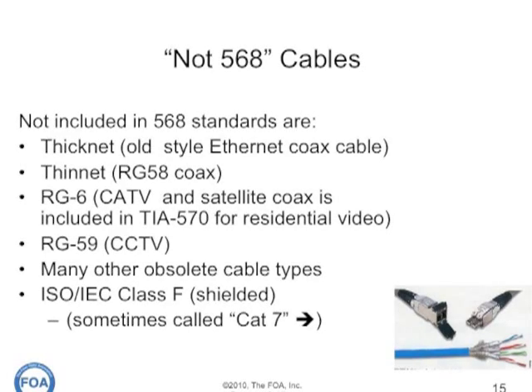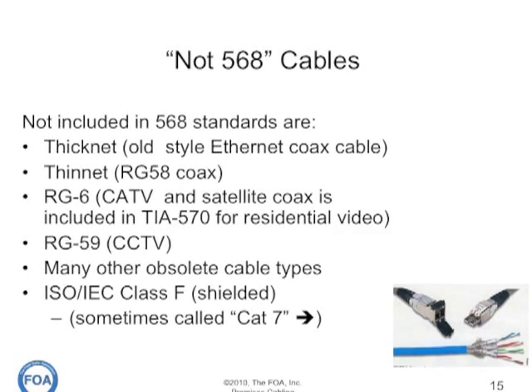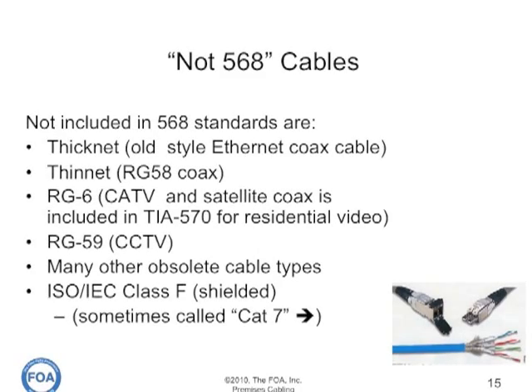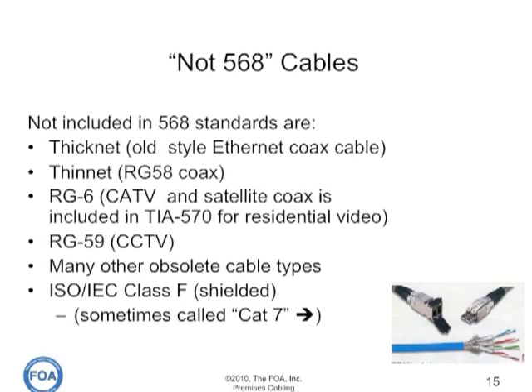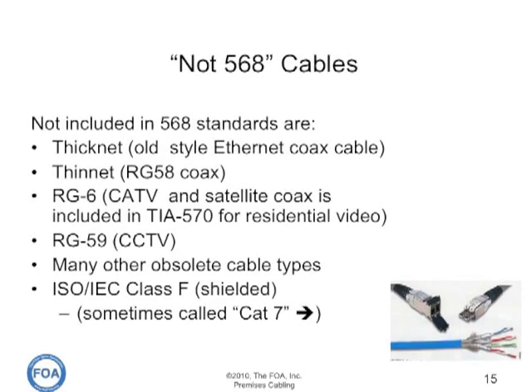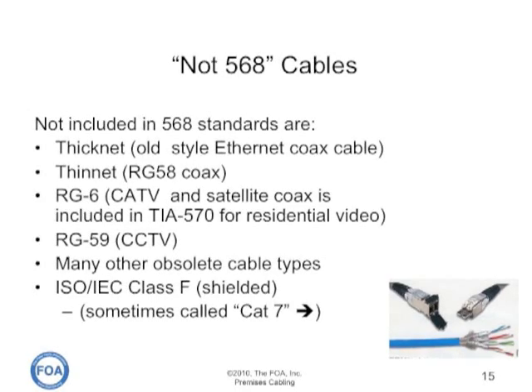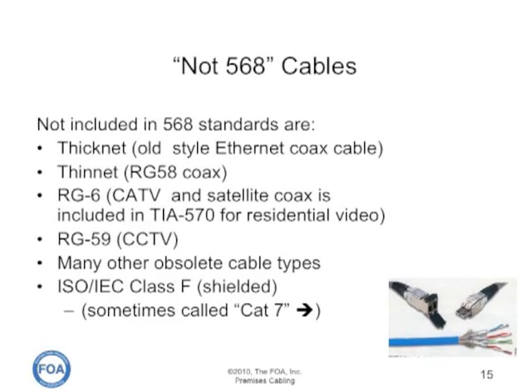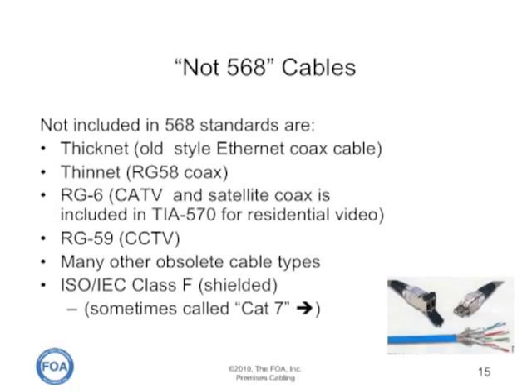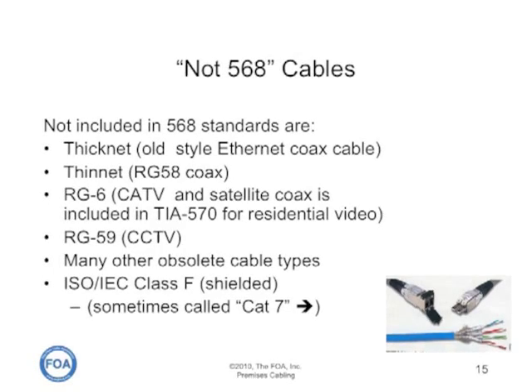Numerous cables used for networking and voice over the years are no longer included in 568 and ISO IEC 11801 international standards. Not included are any coax for thick net — the old Ethernet coax cable — or thin net, the smaller Ethernet cable. Also excluded are satellite or cable TV coax such as RG6, RG59 typically used for closed circuit television, and many other obsolete cable types like IBM cabling. Also not currently included is the ISO IEC Class F shielded cable, sometimes called Category 7. As of this video, Category 7 is finally being considered by the TIA in the U.S. but is not yet a standard.